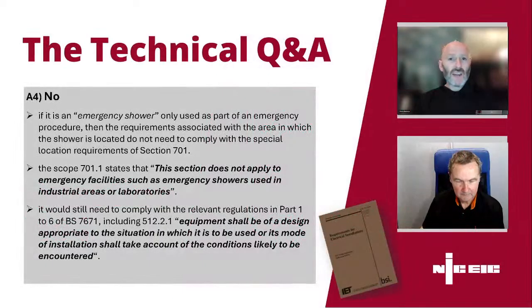Going to throw a straight no in there, Sam. A definitive no. I'm going to give a bit of explanation behind it. What you've got to be mindful of is special locations, there's information available in there. If it is an emergency shower, as the topic we're talking about is, and it's only used as part of an emergency procedure, then the requirements associated with the area of the shower and its location do not need to comply with the special location requirements of section 701 in BS 7671. It's quite clearly stated this section does not apply to emergency facilities such as emergency showers used in industrial areas or laboratories. Obviously, it still needs to comply with all other relevant regulations, parts 1 to 6 of BS 7671.